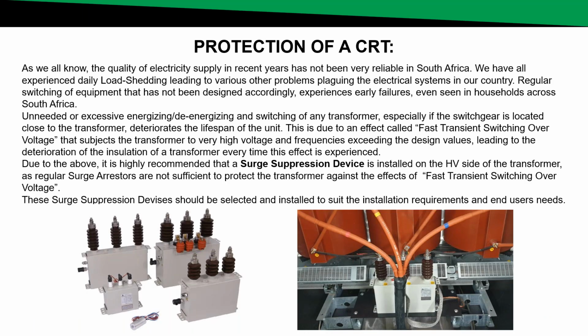Another form, as we all know, we all battle with the quality of electrical supply in South Africa. And we all know what detrimental effects load shedding has on electrical equipment. Unneeded and excessive energizing and de-energizing and switching of any transformer, especially if the switchgear is located close to the transformer, deteriorates the lifespan of the unit. This is due to an effect called fast transient switching overvoltage that subjects the transformer to a very high voltage and frequency, usually exceeding the design value of the transformer, leading to the deterioration of the insulation and can even lead to detrimental or catastrophic failure of the transformer.